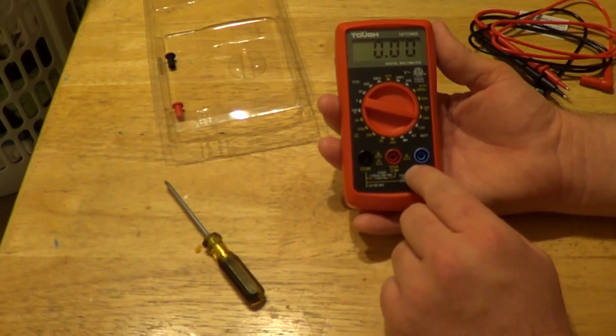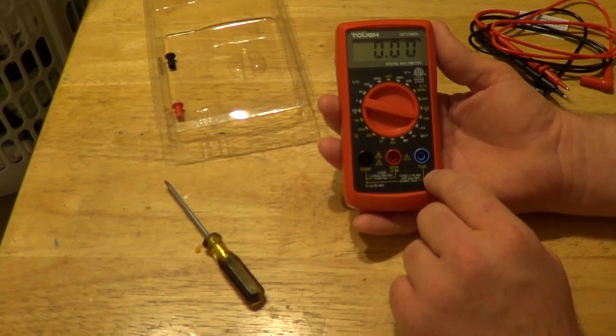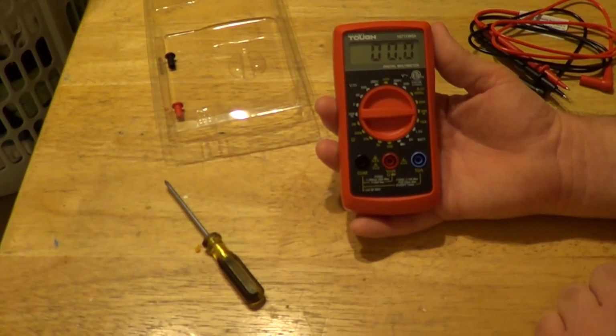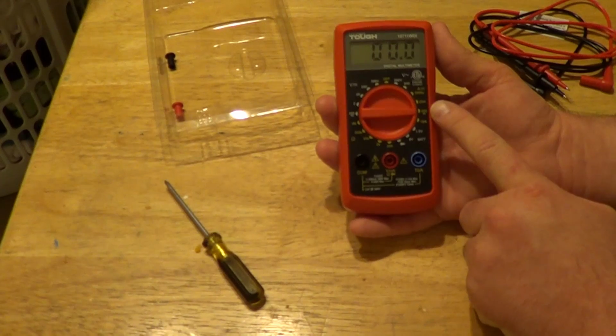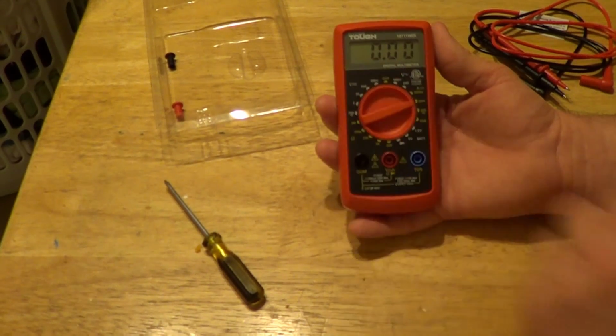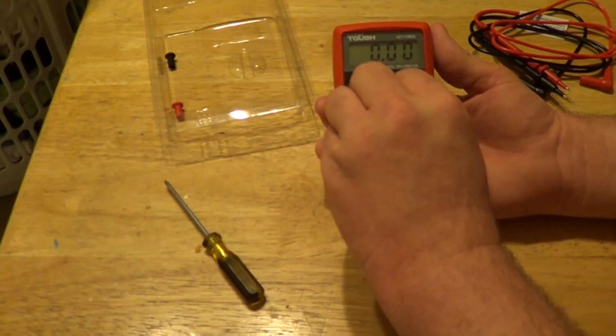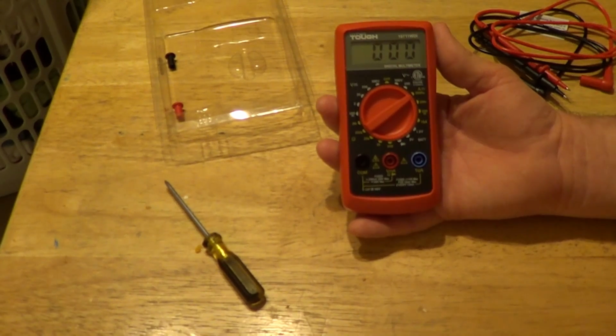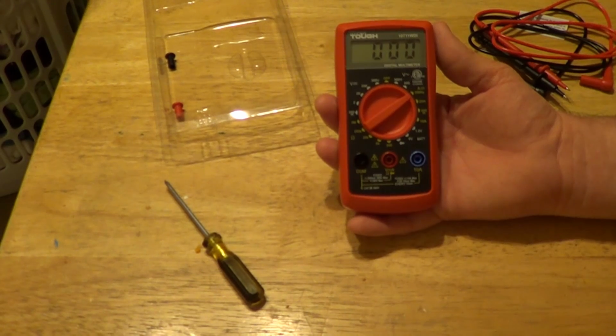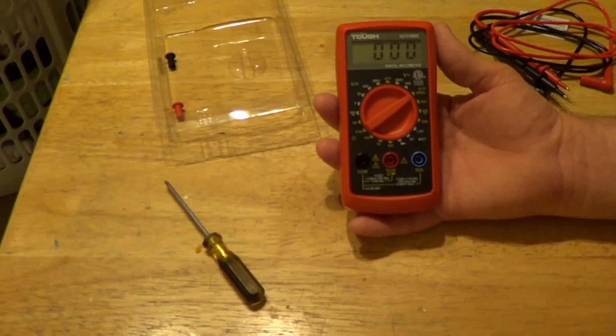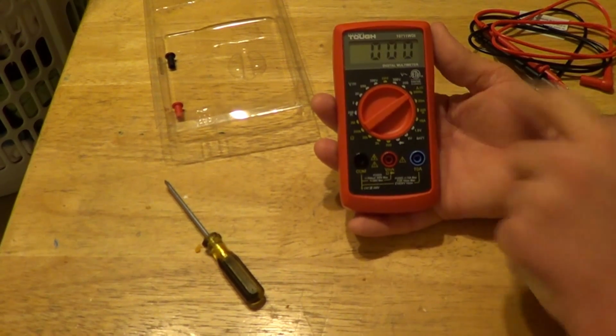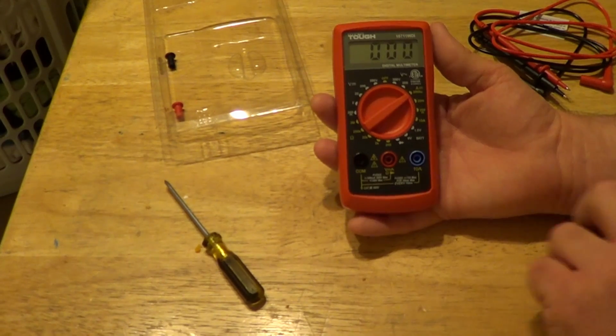So you can use it if you want, but I don't see a great reason to. The smaller current testing ranges might come in handier - we have 200 milliamp, 20 milliamp, and 2000 microamp testing ranges. That microamp range is actually a bit high for some applications, but if you were going to test something like a flame sensing rod inside a furnace, which produces a small electrical current when working properly, the microamp range is for you.